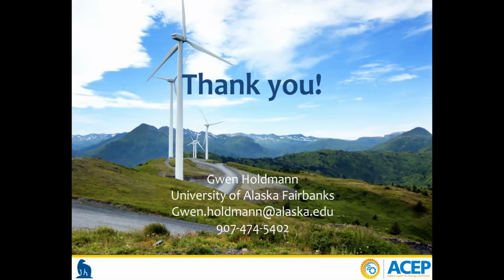So it was approximately 4 years after the original power plant was operational. One thing to think about is the materials used in these geothermal power cycles. There are real challenges sometimes with certain materials. The geothermal fluid can be pretty aggressive, often containing some sulfur and things like this that can create issues. In this case, the demonstration original plant used tubes that had copper as a component, and those did not hold up to the geothermal fluid.